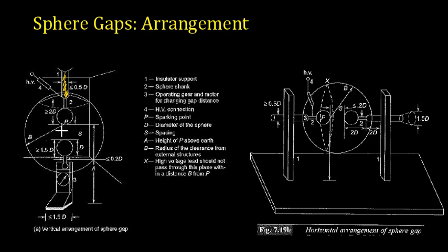The diameter of the sphere is provided, and the spacing between them, the height of this particular sparking point above the ground, and the radius. So this is a radius of clearance from external structures. This particular structure has to be kept away from external structures at some particular distance. That radius is given as B, and the high voltage lead should not pass through its plane. So the high voltage lead has to be away from this particular plane. Okay. So this is your vertical arrangement, and this is a horizontal arrangement.